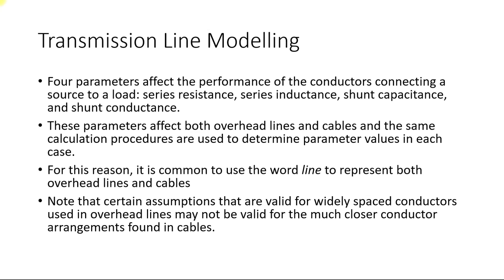For this reason, it is common to use the word 'line' to refer to both overhead lines and cables, since both have the same type of quantities. Note that certain assumptions valid for widely spaced conductors in overhead lines may not be valid for the closer conductor arrangement in cables — capacitance being the best example of this.